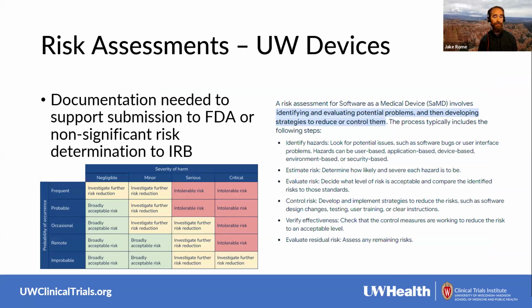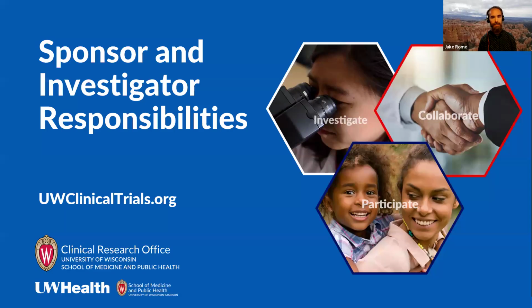If you're making your own devices, you should be doing risk assessments as you're developing it to make sure that you're documenting everything you need to do to make the case to the IRB or the FDA that this is a non-significant risk device. Again, as the developer of the device, as the manufacturer, it's your responsibility to manufacture it in a way that reduces the risks as much as possible whenever possible. So something to consider for those of you developing either hardware medical devices or software medical devices.